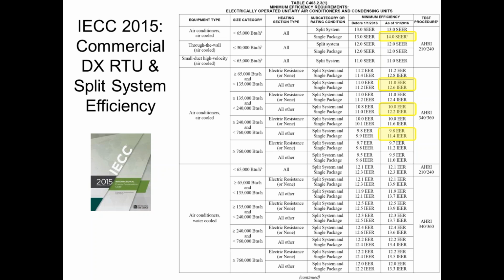So if I got a quote-unquote 10-ton unit, that's 120,000 BTUs of cooling, I need to have 11 EER and 12.6 IEER. I have to do both. It's not one or the other. I have to meet both metrics.